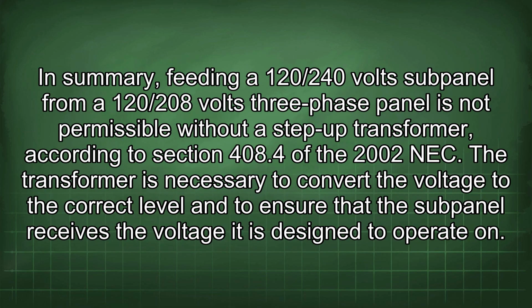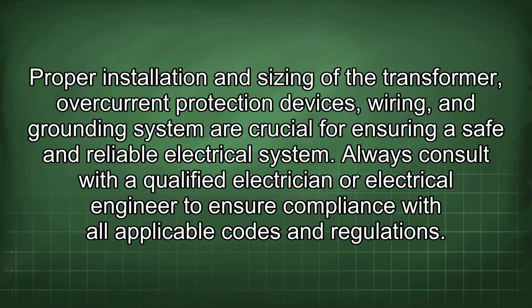In summary, feeding a 120/240 volt subpanel from a 120/208 volts three-phase panel is not permissible without a step-up transformer, according to Section 408.4 of the 2002 NEC. The transformer is necessary to convert the voltage to the correct level and to ensure that the subpanel receives the voltage it is designed to operate on. Proper installation and sizing of the transformer, overcurrent protection devices, wiring, and grounding system are crucial for ensuring a safe and reliable electrical system. Always consult with a qualified electrician or electrical engineer to ensure compliance with all applicable codes and regulations.